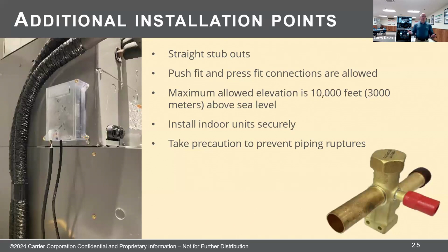Indoor units, this is kind of a standard practice. Just make sure it's installed securely, and we want to reduce the risk of that thing moving around and rupturing any of our refrigerant lines. Can't use these on airplanes. Not an issue in our area, but the maximum allowed elevation is 10,000 feet above sea level. Nowhere in our market is above that, so I didn't bother to find out what the reason was.